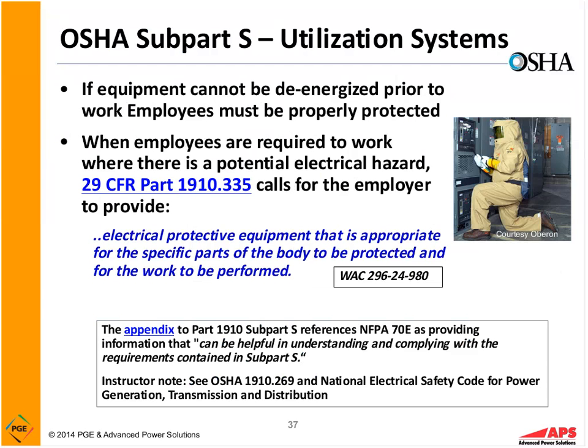Please look at the OSHA requirements and look at the exceptions to that. OSHA Subpart S, again: if equipment cannot be de-energized prior to work, then employees must be properly protected. So when employees are required to work where there is a potential hazard, what does 1910.335 call for? It calls for the employer to provide electrical protective equipment that's appropriate for the specific parts of the body to be protected and the work to be performed. Now notice, if we look at the appendix to 1910 Subpart S, in the little box down below, it tells you to refer to 70E as providing information that can be helpful in complying. Now you notice this is what I would call one of their blanket requirements.